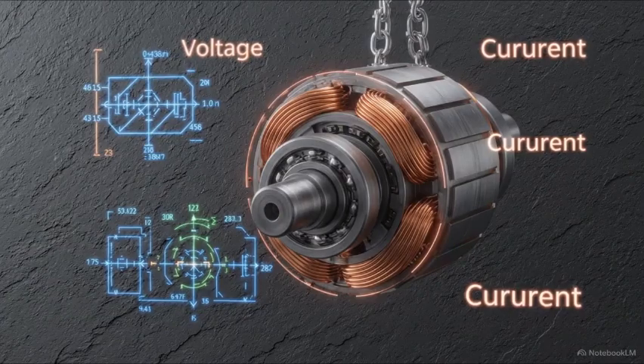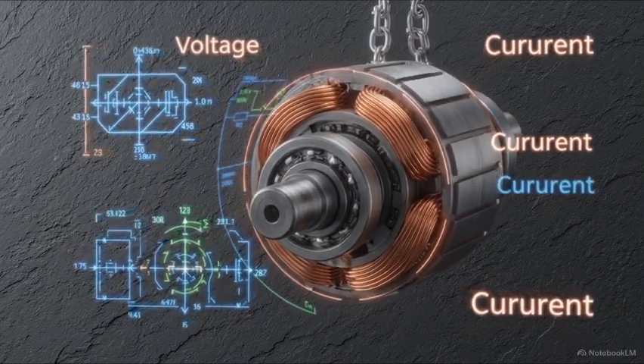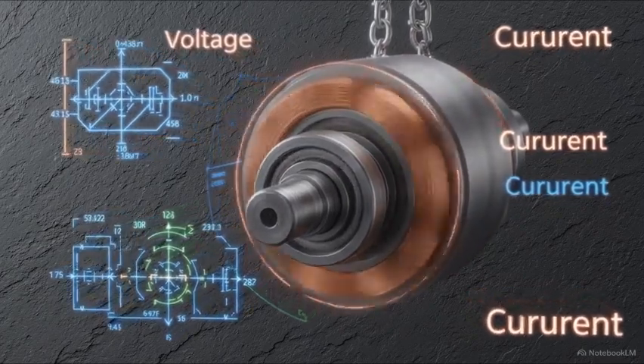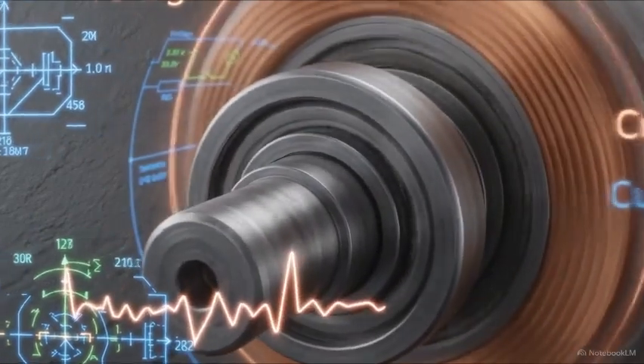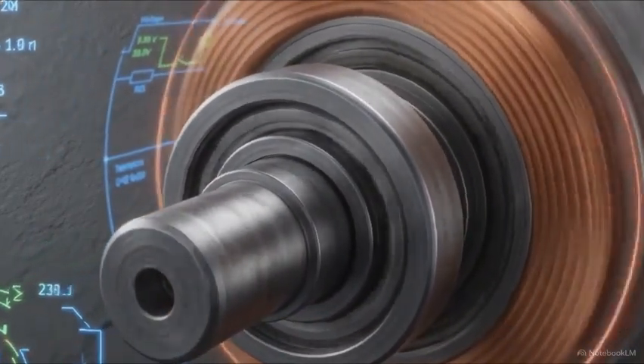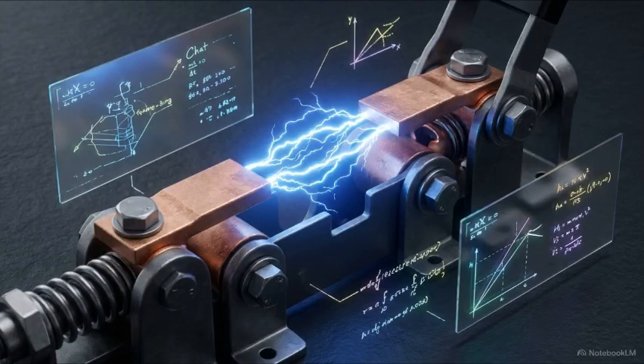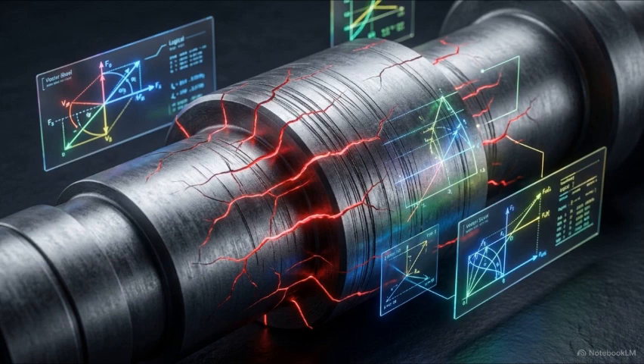instantly. But electricity itself has no mass. To maintain continuous flow, mechanical power pushing the generators must perfectly match the electrical power demanded in real time. When grid demand suddenly drops or spikes, electrons don't absorb the shock. That physical force is absorbed directly by the spinning mechanical turbines.